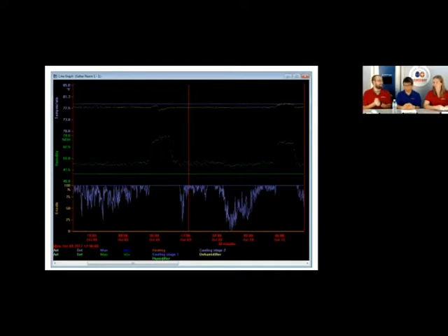That's good. This graph can be really useful for us, for Curtis here, in terms of changing the set points in your system, in terms of delays and that sort of stuff, and fine-tuning your ventilation. So if you have several graphs showing an issue that was happening in your ventilation, you can send those in to us, and from them we can judge what needs to be changed in terms of the configuration in your equipment. Maybe we need a longer delay, or maybe we need to speed up that PID loop, something like that.